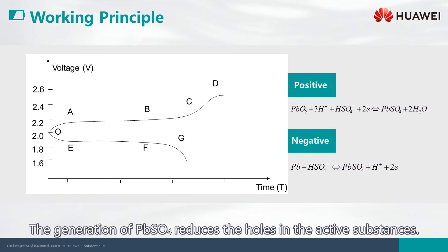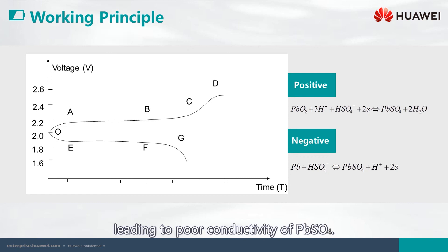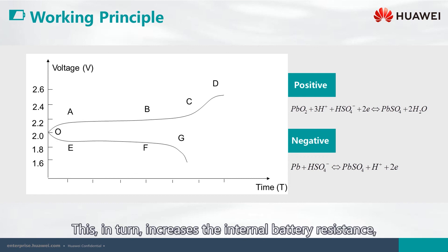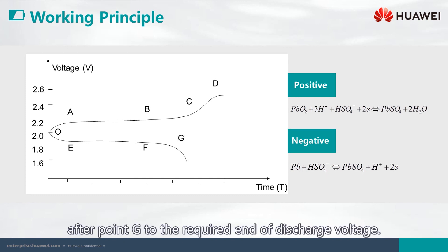The generation of lead sulfate reduces the holes in the active substances. This makes it more difficult for sulfuric acid to enter the micropores, leading to poor conductivity of lead sulfate. This, in turn, increases the internal battery resistance, causing the terminal voltage to drop dramatically after point G to the required end of the discharge voltage.